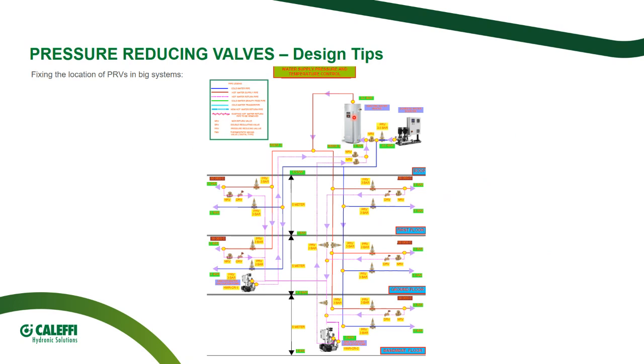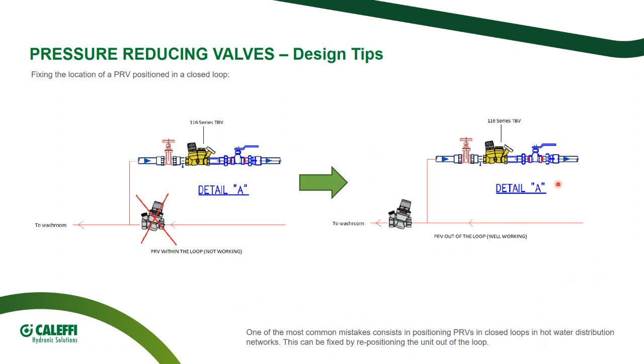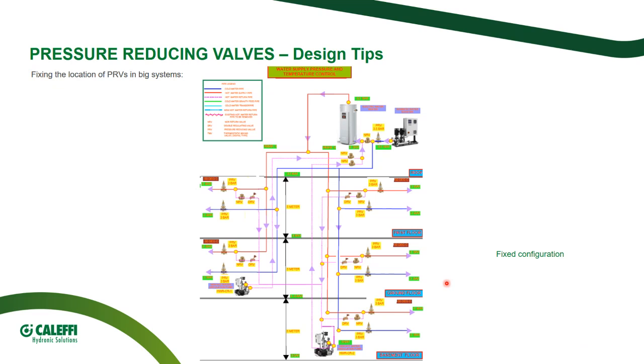where, as you can see, there is a calorifier with the recirculation loop with balancing with a double regulating valve. But as you can see, the PRVs for hot water are within the recirculation loop. So the final consequence of this situation will be lack of recirculating hot water, causing serious issues. So our recommendation to the designer was, okay, take the PRV just out of the recirculation loop, so solve it like this, and everything was fixed.